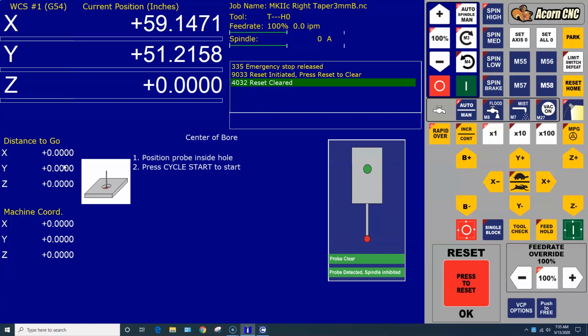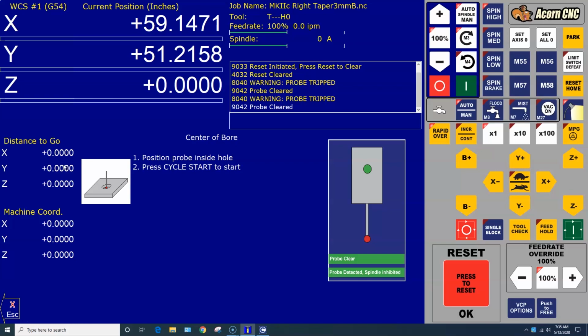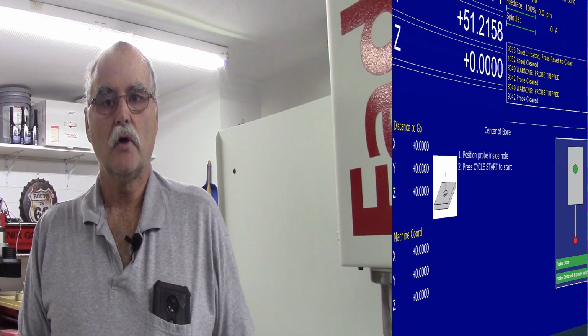So I'm going to go ahead and trip it. And there you see it's tripped. I'm going to release it. And it's back to normal. It's clear. I'm going to trip it again. It's tripped. So great. It looks like we've got it wired up correctly and it's functioning okay. Okay, what we're going to do now is we're going to manually test the probe in the machine. We're not going to probe a part, but we're going to use our finger just to trip the probe.